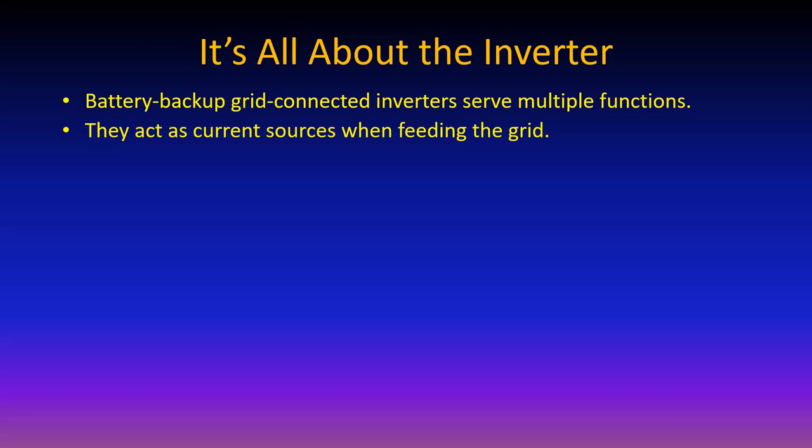IEEE 1547-2018 also allows the utility some control over the power factor of the generation. So if the utility power factor is low or inductive, the inverter can effectively come in as capacitive - acting like a big capacitor - because it's simply a matter of telling it what phase angle to maintain as a difference between the current and the voltage.